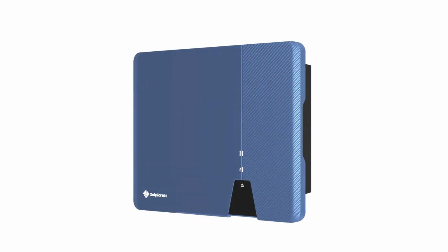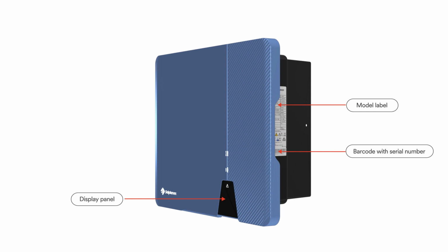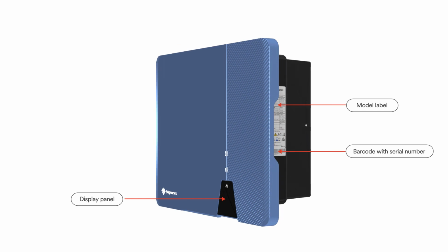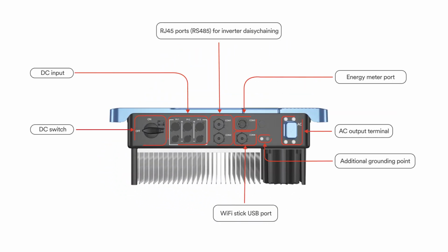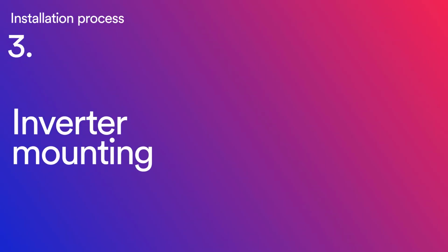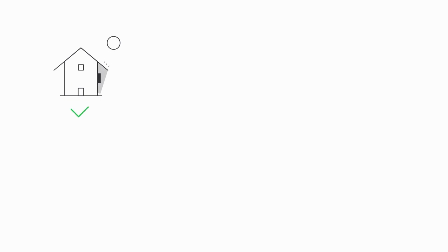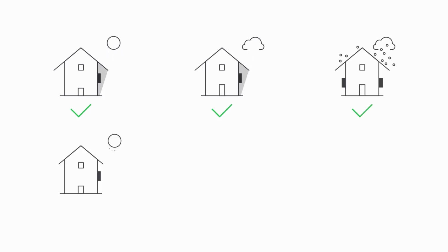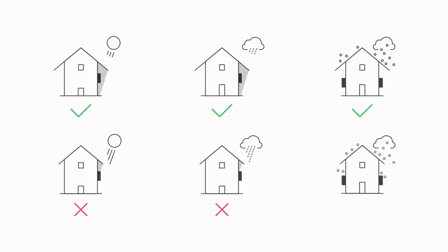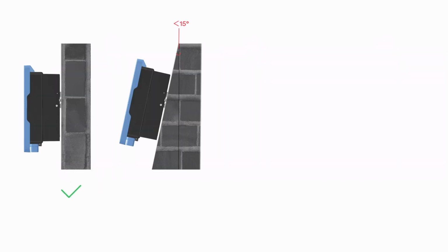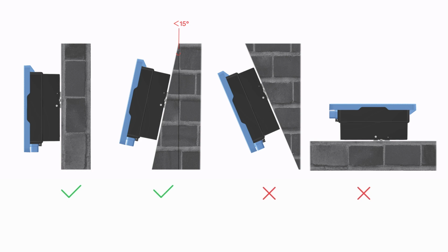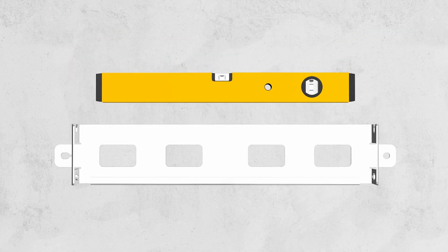Solplanet inverters are efficient and reliable. All product information is on the outside of the inverter and connections are conveniently placed on the bottom. Avoid exposing the inverter to direct sunlight, rain, and snow to ensure optimal operation and extend service life. Mount the inverter on a vertical wall. Position the wall bracket horizontally.